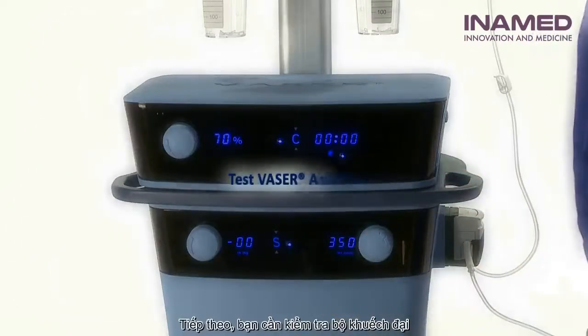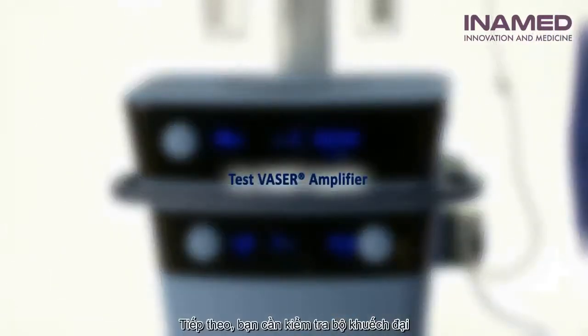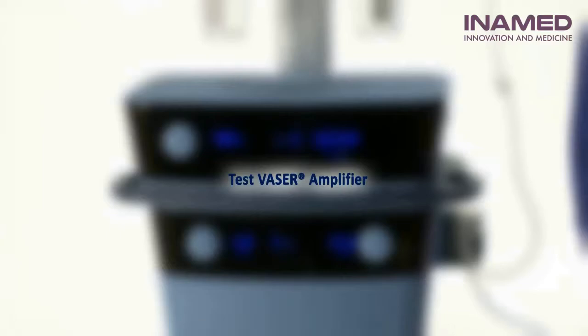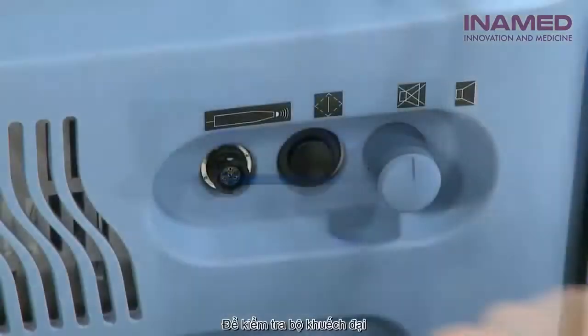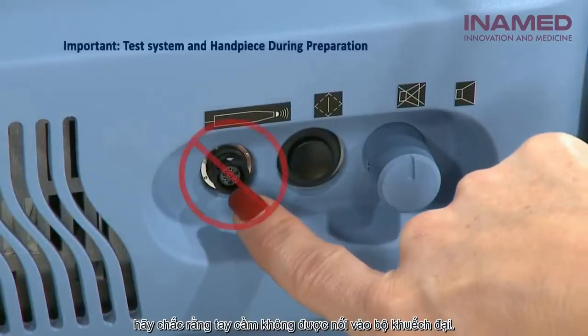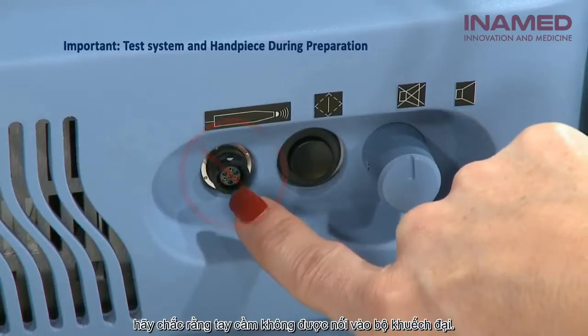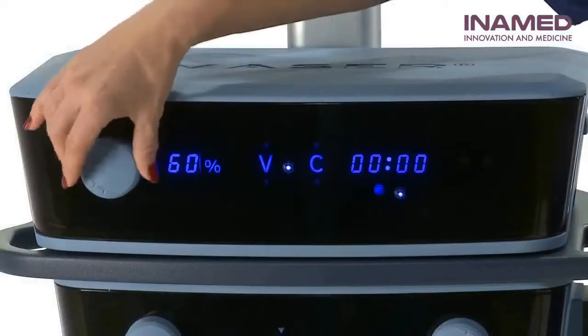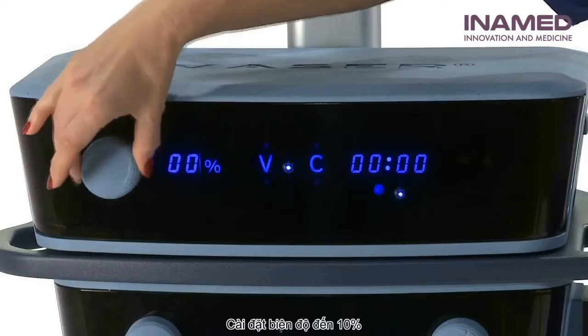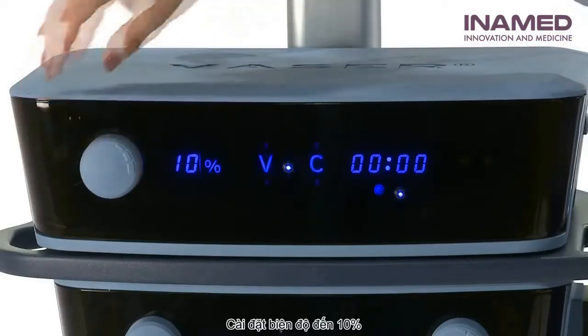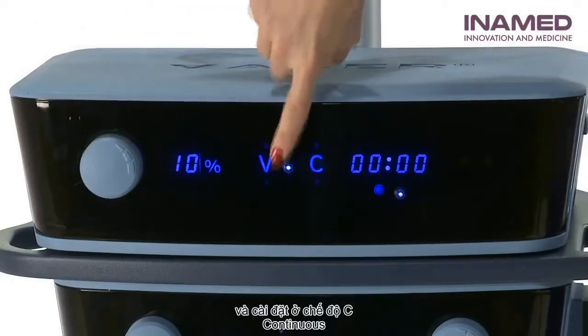Next, you will need to test the Vaser amplifier. It is very important to ensure the Vaser amplifier and the Vaser handpiece is working properly before the patient arrives. To test the amplifier, ensure that the Vaser handpiece is not connected to the amplifier. Set the amplitude to 10%. Set the mode to C, continuous.